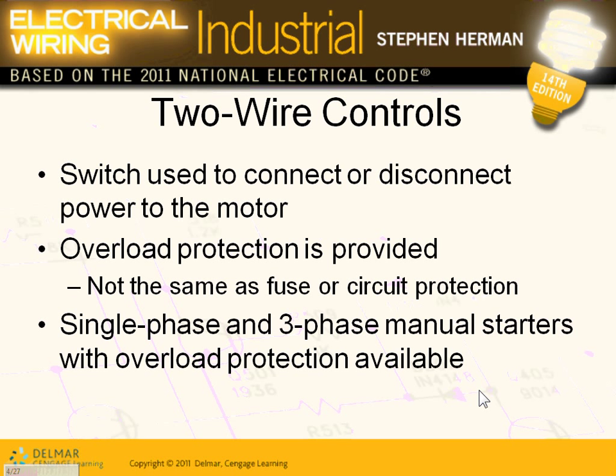Would you do this with a saw or a machine? If I'm cutting through an industrial machine and the power went out — I went outside waiting for the power to come back. Do you want the machine to restart automatically when the power comes back? Danger. So two-wire is mostly used with HVAC equipment and a couple of specific applications. The other one is called three-wire control, which we'll look at in a second.